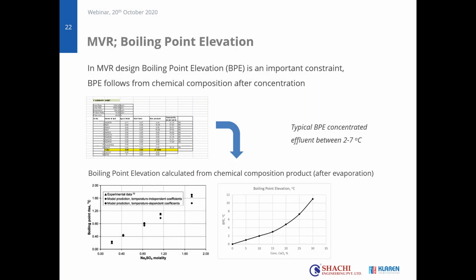The second key element starts with saying something about boiling point elevation and how this reflects to the design, I will say later. But to start with, what is boiling point elevation? If we have a wastewater, an effluent that contains dissolved salts, then these dissolved salts influence the boiling point. That means that effectively your liquid will boil at a higher temperature than what you would expect with the pressure. For example, at atmospheric conditions, normally the water would boil at 100 degrees, but with boiling point elevation, it could boil at 103, 104, 106 degrees. So typically, for concentrated effluents, this boiling point elevation will be between 2 and 7 degrees.